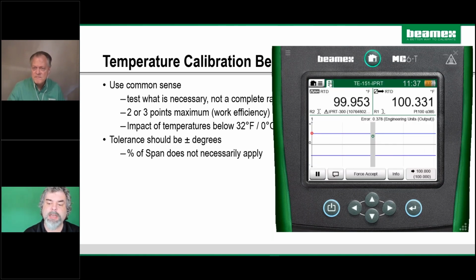Yes, sir. One comment I wanted to make is that, I guess I'll call it a misconception. I get this a lot, and that is, I don't need to test temperature probes because they either work or they don't. They're either good or they're bad. And this example is proving the fact that, well, yeah, it's working, but it's not good. There's a half a degree offset in the probe that you're never going to know unless you actually test it. And if your process is important enough, then you actually do need to test it. And if it's not, then you don't.